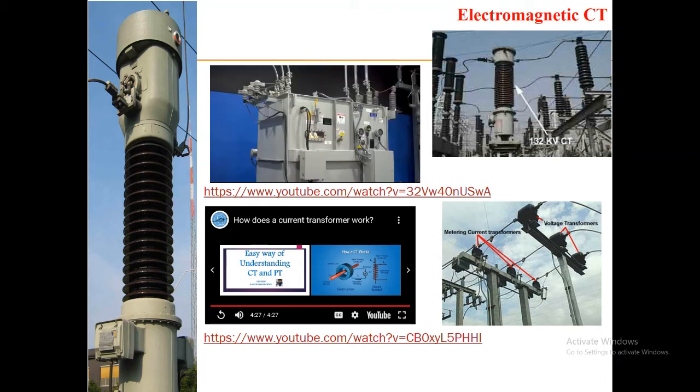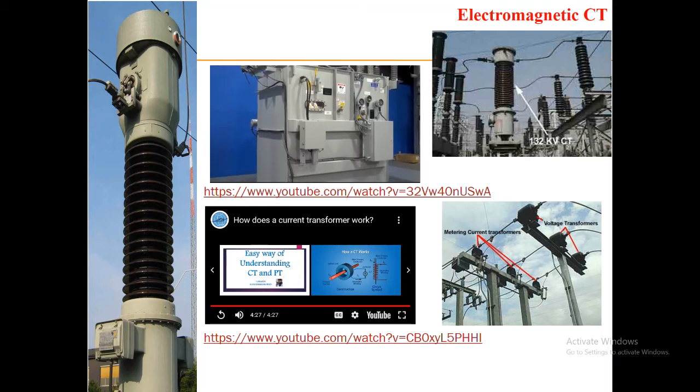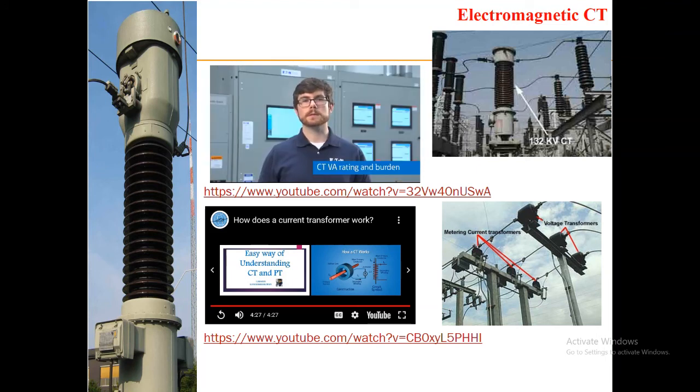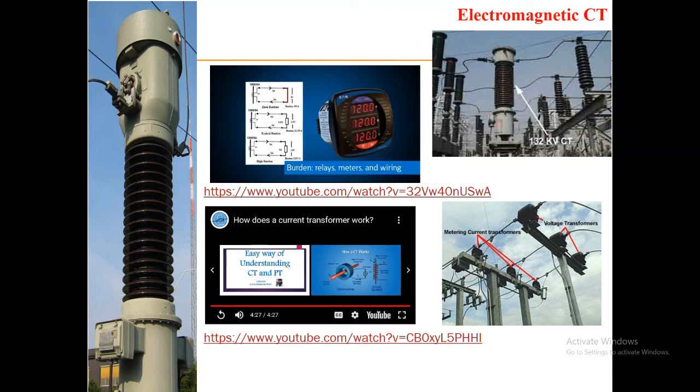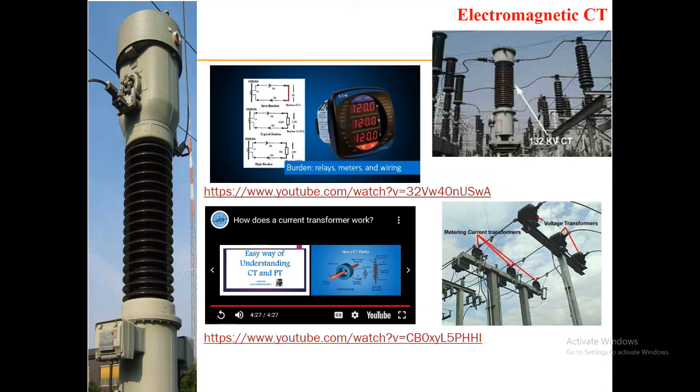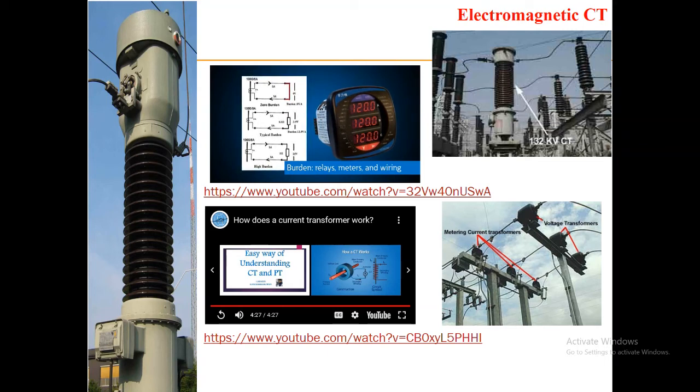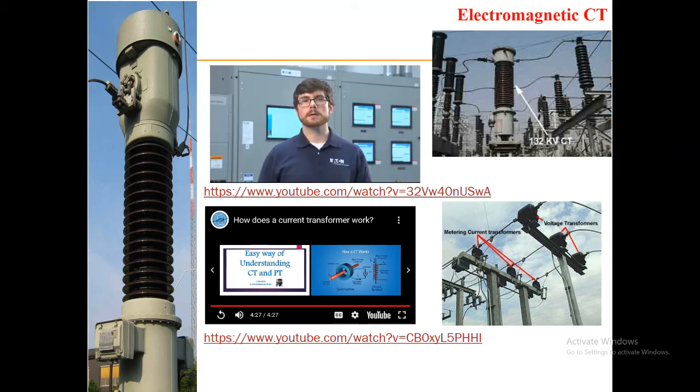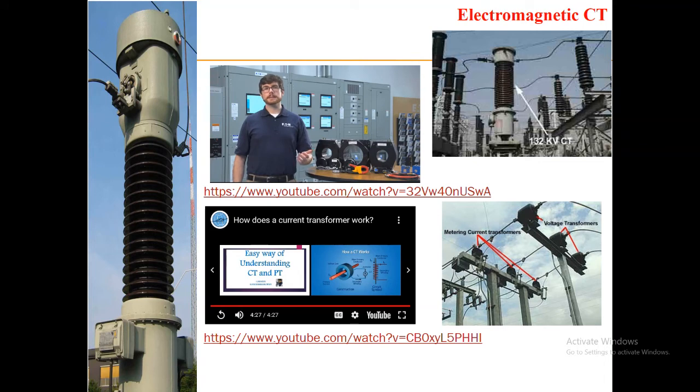Additionally, CTs can also experience a phase shift between primary and secondary windings which can range between a few tenths of a degree up to 6 degrees. That phase difference can make power measurements incorrect, even to the point that power may look like it is incorrectly flowing out of the load. Like all transformers, CTs have volt-ampere or capacity ratings. CTs have limits to the number of devices and length of wire that can be connected to its secondary side, which is called the burden. Items that contribute to burden are relays, meters, and wiring. The best way to reduce burden is to keep the conductors between the CT and the metering devices as short as possible or increase the wire size to reduce resistance. The burden for today's modern electronic relaying and metering is very low compared to older equipment, but care must be taken to ensure CTs are not overloaded or inaccurate current measurements or protection will result.